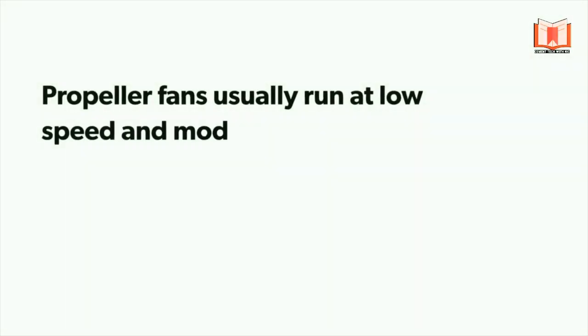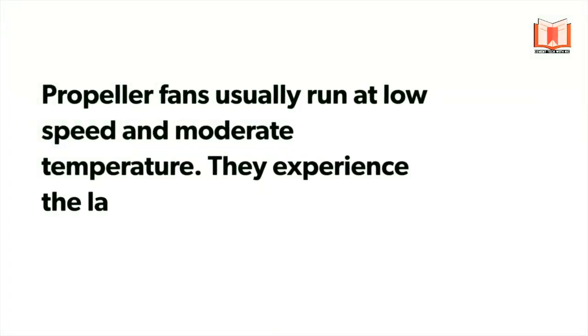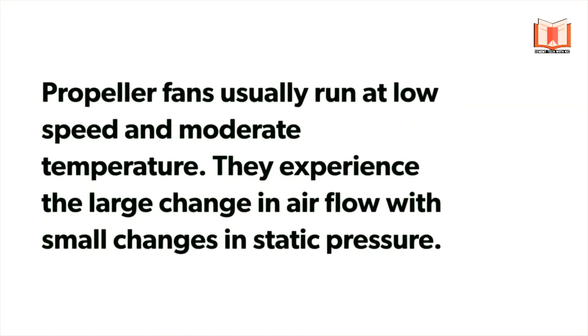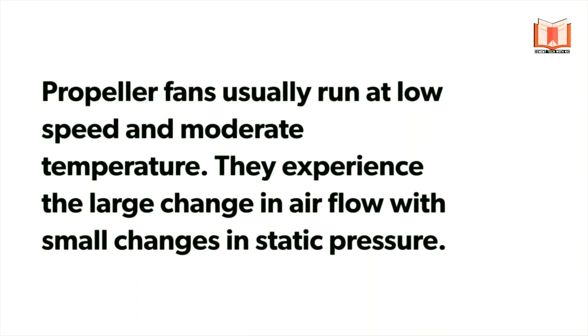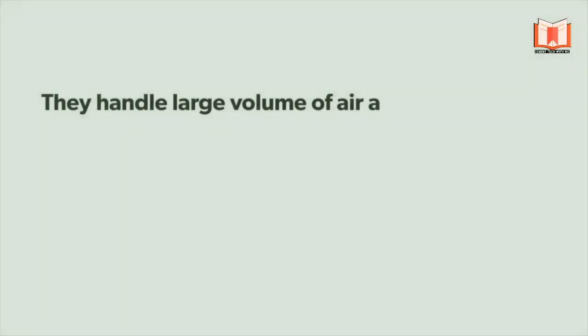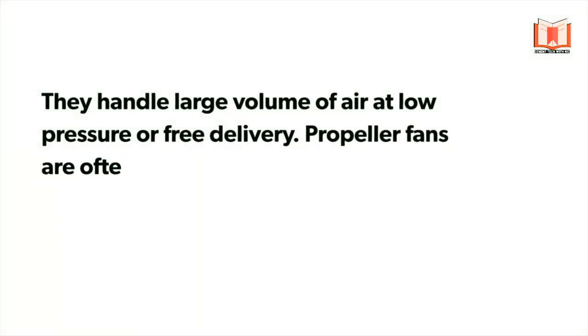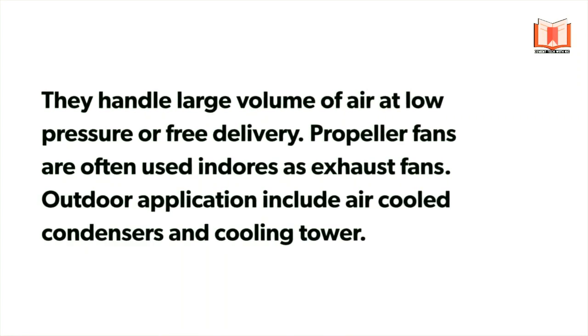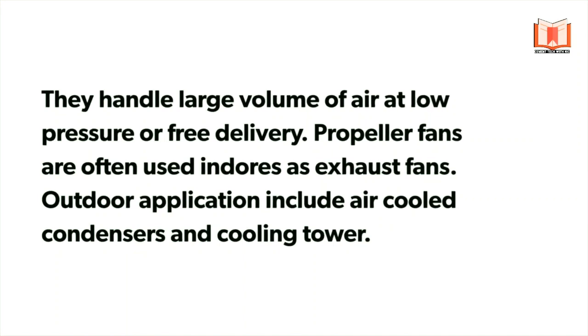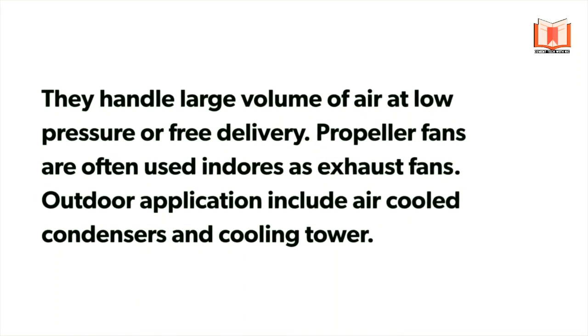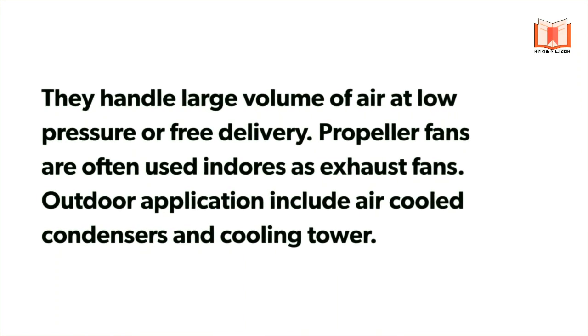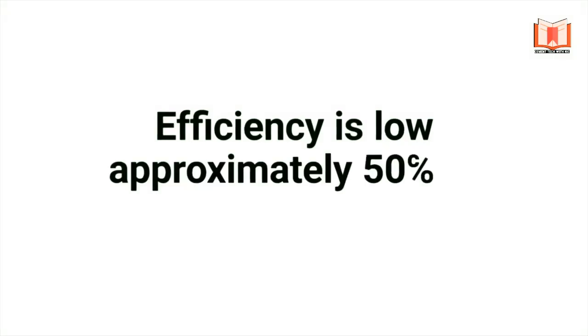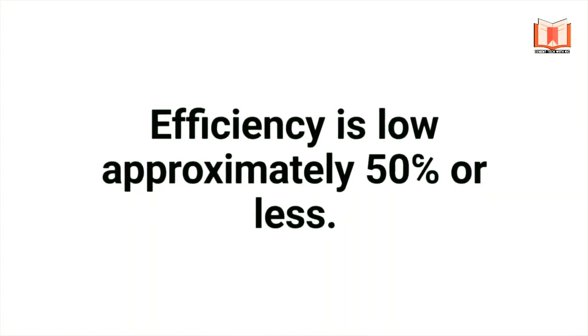Propeller fans usually run at low speed at moderate temperature. They experience large changes in airflow with small changes in static pressure. They handle large volumes of air at low pressure or free delivery. Propeller fans are often used indoors as exhaust fans; outdoor applications include air-cooled condensers and cooling towers. Efficiency is low, approximately 50% or less.